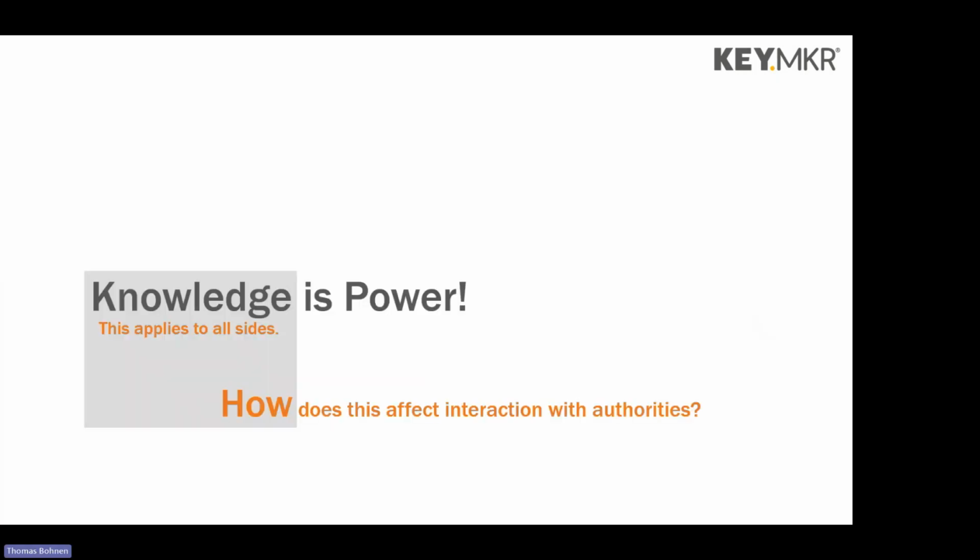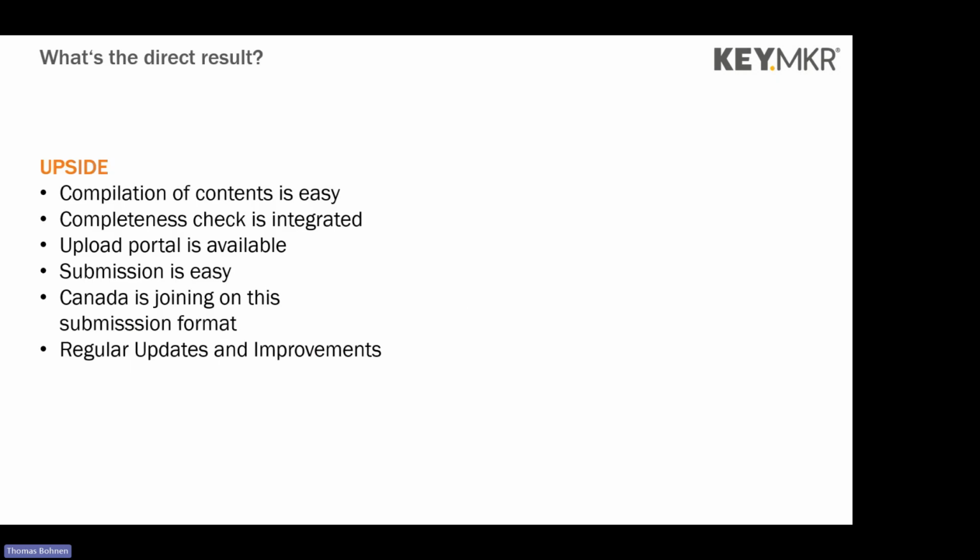Knowledge is power, you know that. But how does this affect the interaction with authorities, or in Europe, with the notified bodies? Now, think of this process and what you have there. There's an upside. The compilation of contents is guided. You have a handrail, this red and green handrail where you go along, and if you follow that properly, you'll end up with a complete submission.